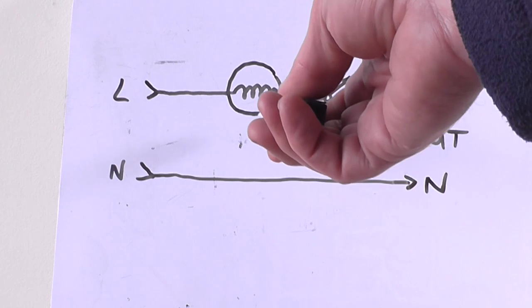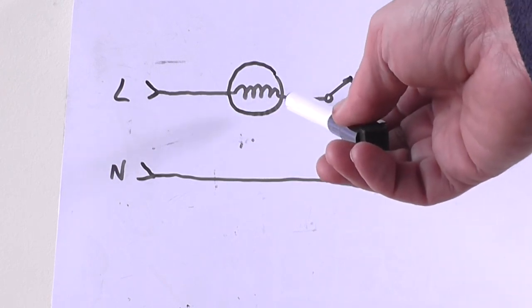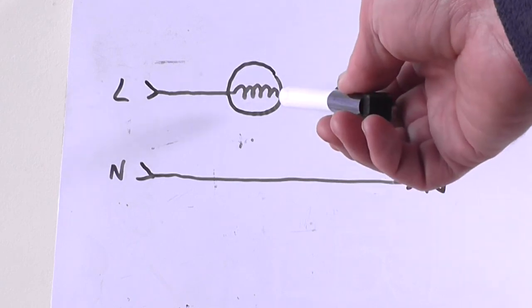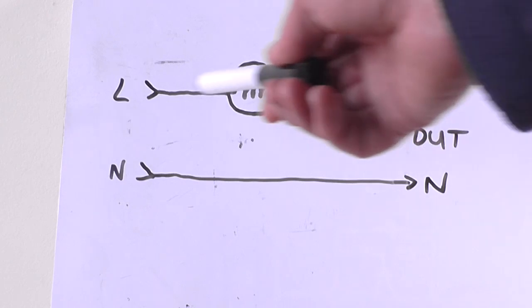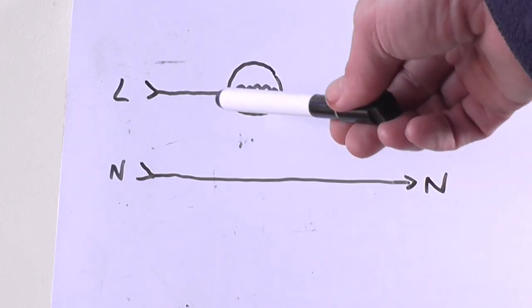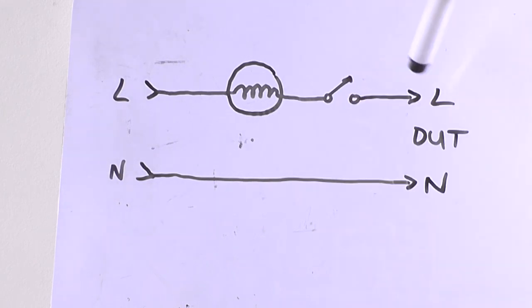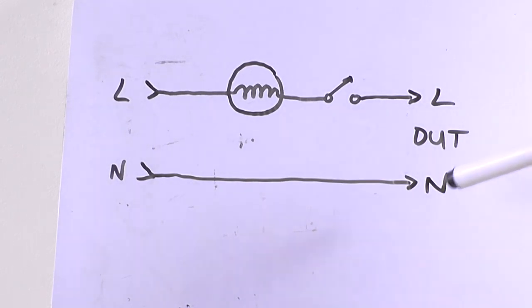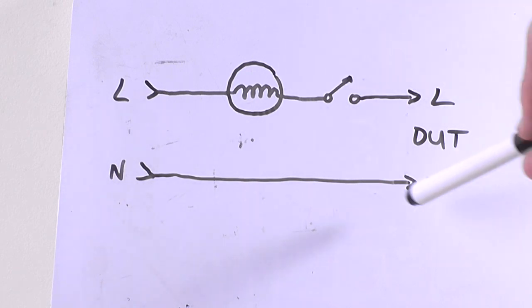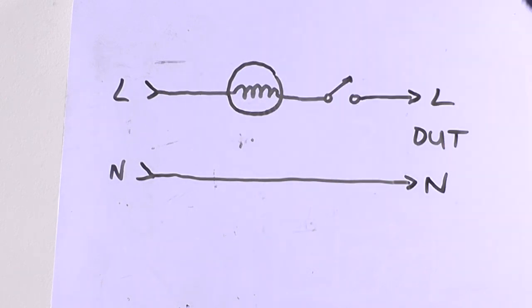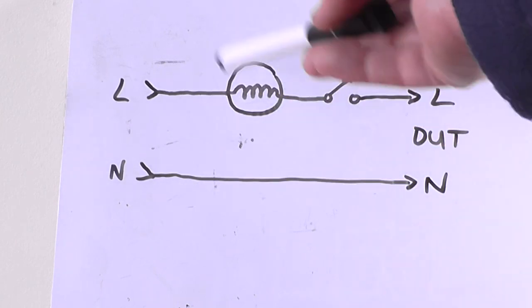This light globe works like a ballast - the more current that flows through it, the higher the voltage drop presented across the line. So the brighter this globe glows, the lower the voltage experienced at the DUT. This means that if these two wires, the live and neutral at this end, were shorted together, basically this is now turned into a desk lamp. If shorted, this light will light at full brightness and will only draw the current through the globe that it requires to light up to its full wattage off the 240 volt line.